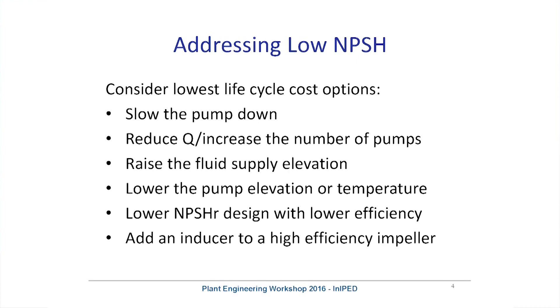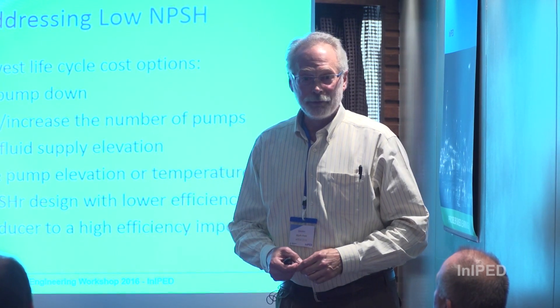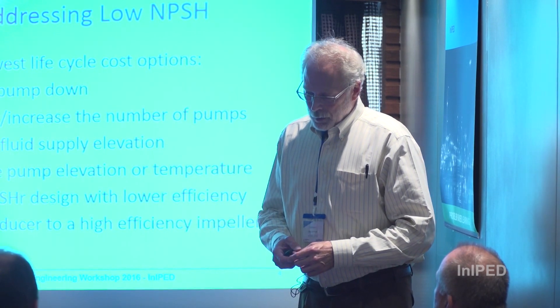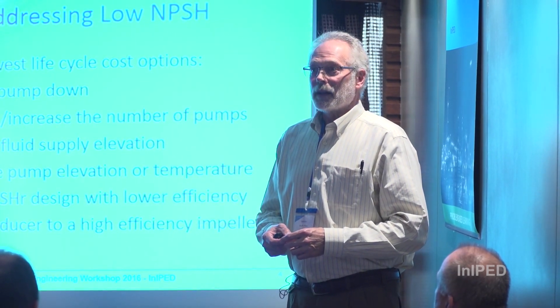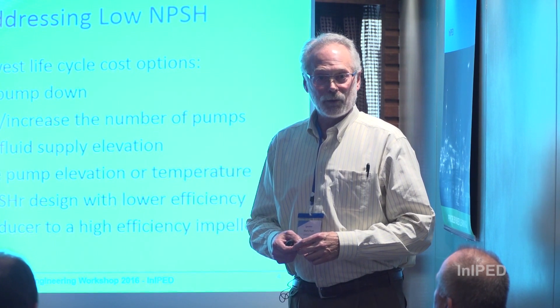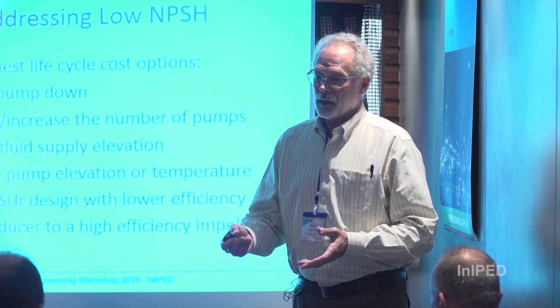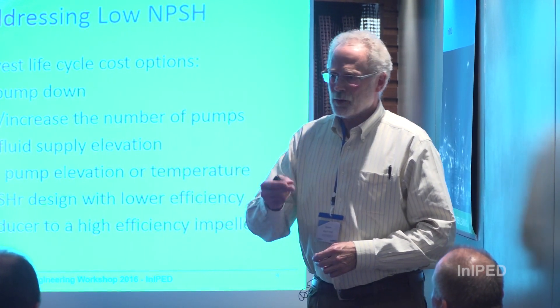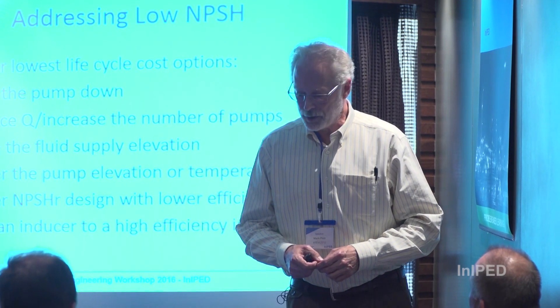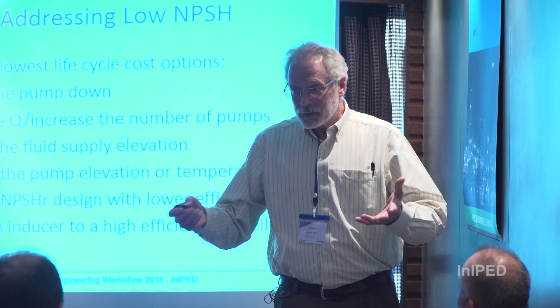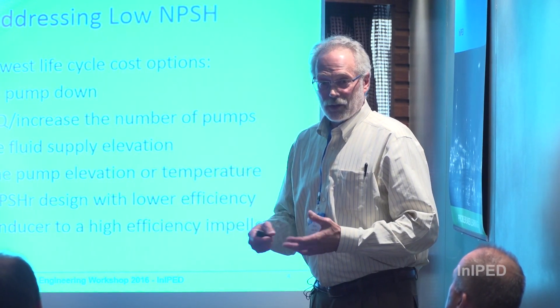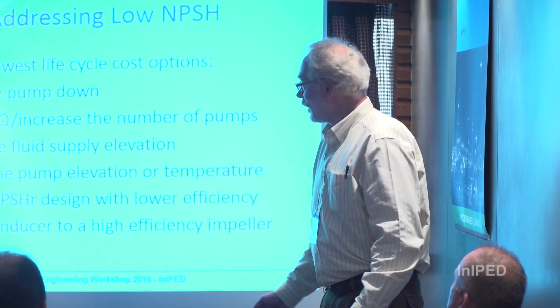For instance, we're working on a dry dock job now where the pump is going to be down in a pit about 50 feet, so it can move enormous amounts of water despite a fairly challenging NPSH. You could also design an impeller for low NPSH, though you'll start compromising efficiency. And finally, what we're really here to talk about: adapting an inducer to a high-efficiency impeller is a very viable option.